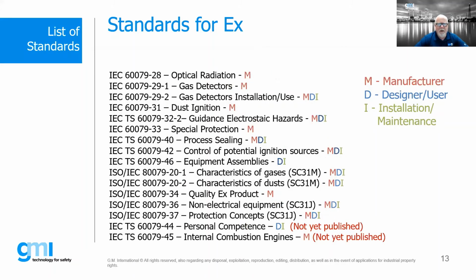You'll see some other ones here, and I'm not going to go through every single one, but a couple are somewhat important to pay attention to. One of the latest is the IEC TS 60079-46. This deals with equipment assemblies. So if I'm a skid package manufacturer taking a bunch of different EX equipment and putting it all together, there's actually a certification scheme for the entire assembly. This has a lot to do with the requirements spelled out in the dash 14 design standard—the selection of appropriate glands, cabling, and installation requirements as part of an overall assembly.